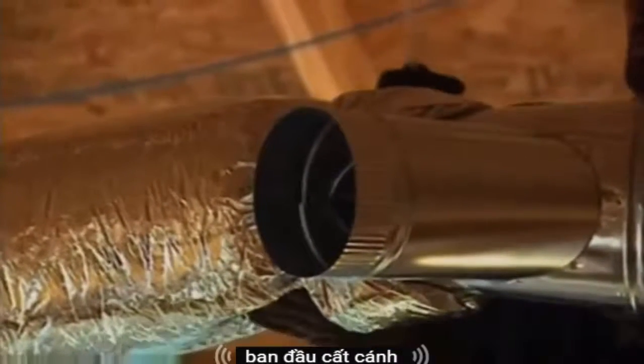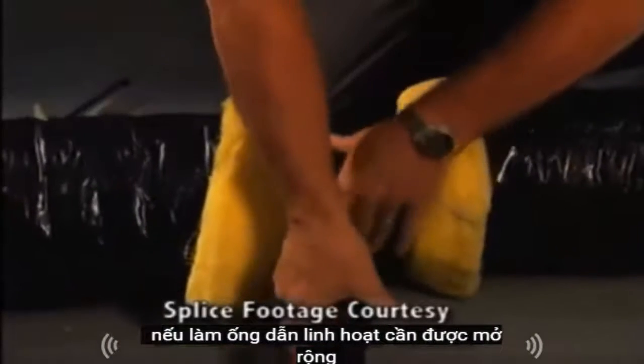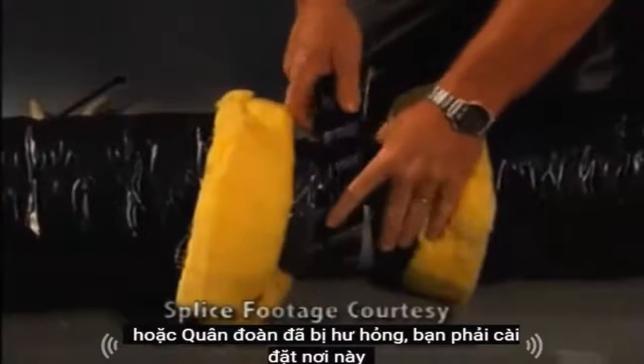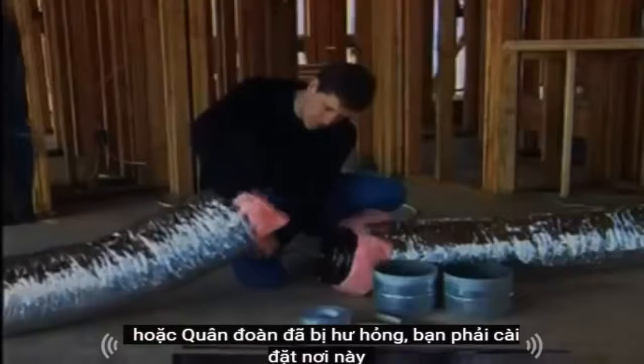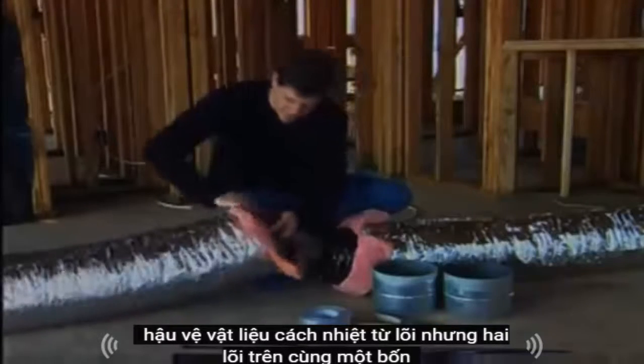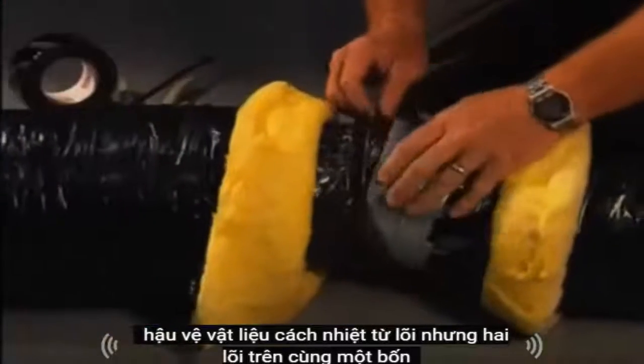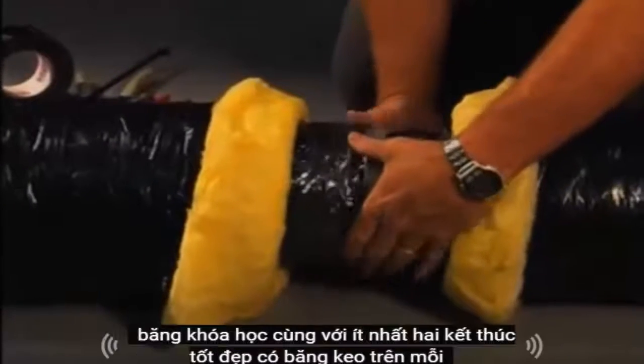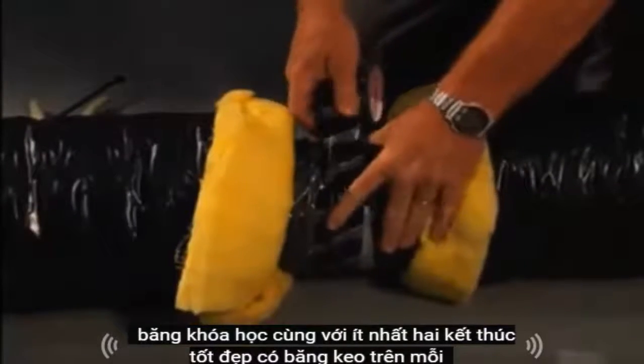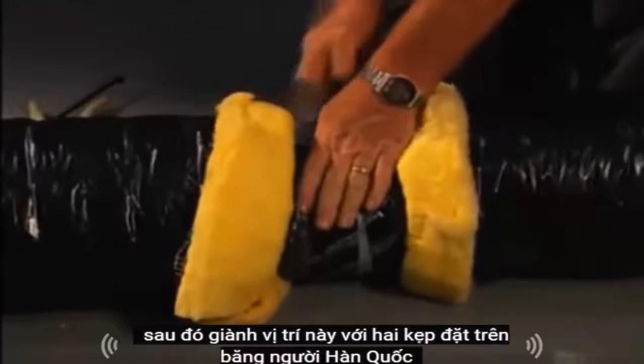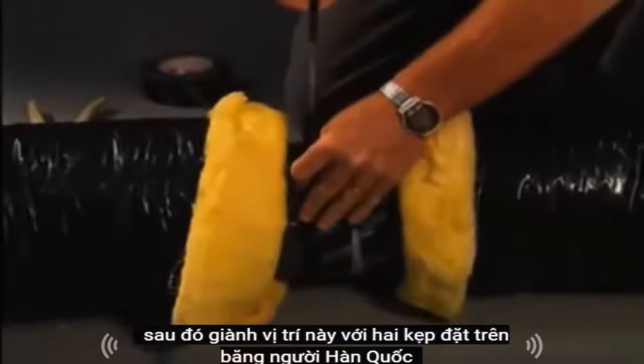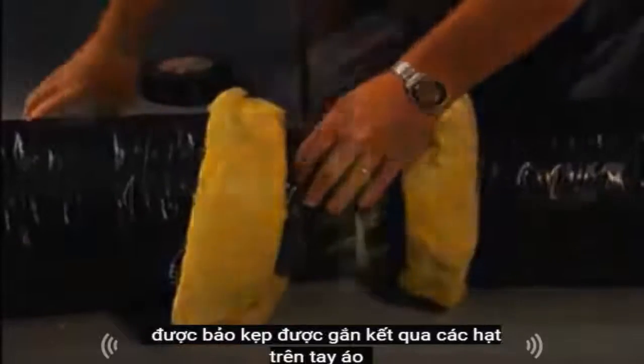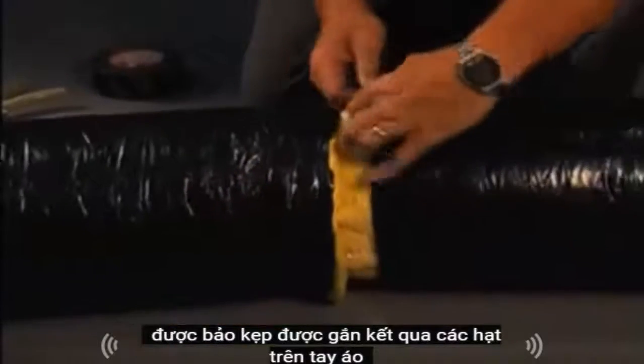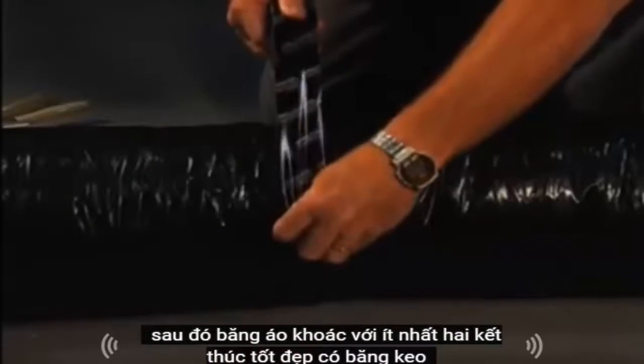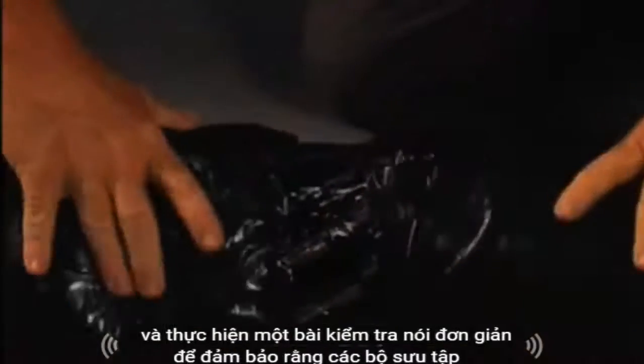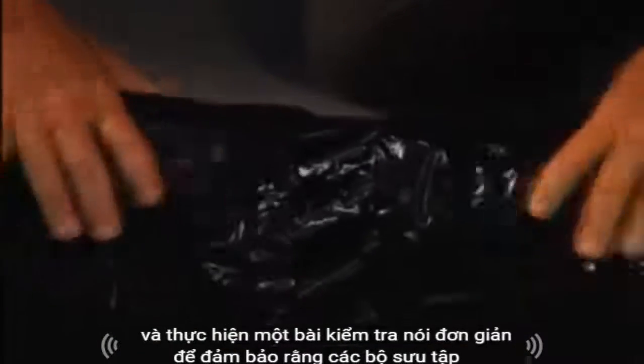If the flexible ductwork needs to be extended or the core has been damaged, you must install a splice. Pull back the insulation from the core. Butt the 2 cores together on a 4-inch length metal sleeve. Tape the cores together with at least 2 wraps of duct tape on each connection. Then secure the splice with 2 clamps placed over the taped core ends. Be sure the clamps are mounted past the beads on the sleeve. Then tape the jacket with at least 2 wraps of duct tape and perform a simple tug test to make sure the connection is secure.